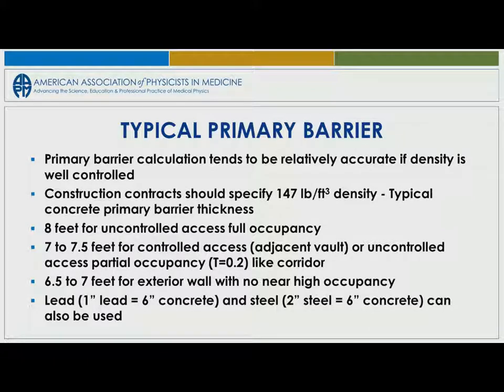7 to 7.5 feet is what you want in an adjacent vault, and any corridor will all go for about 7 to 7.5 feet. If you have an exterior wall with no occupancy nearby, you can take that thickness down to about 6.5 to 7 feet. It'll save you thicknesses. You don't have to buy quite as much concrete and take out quite as much space if you can let occupancy work in your favor.